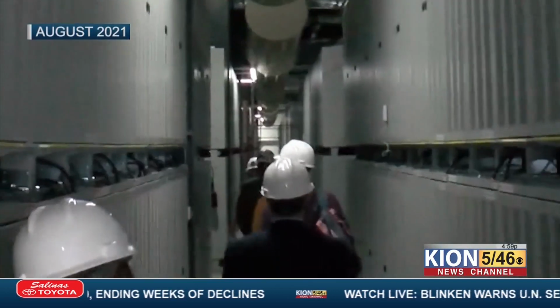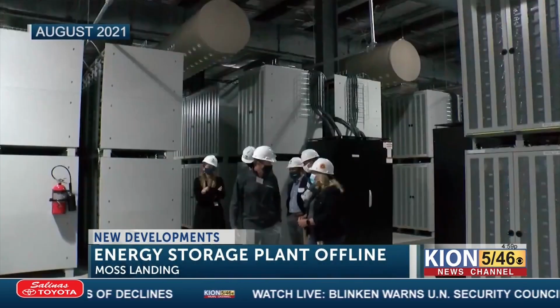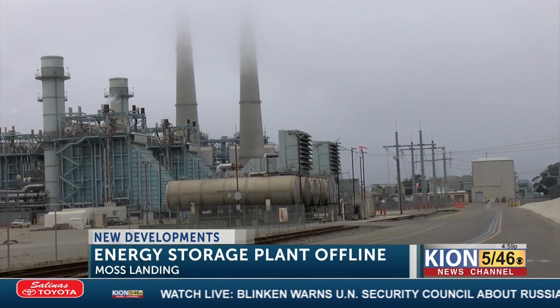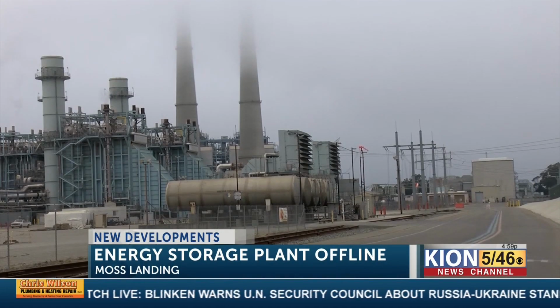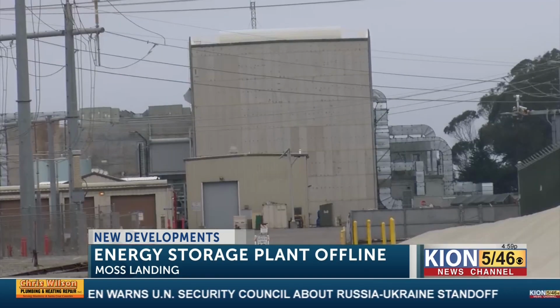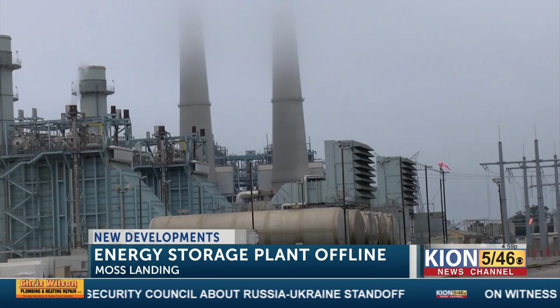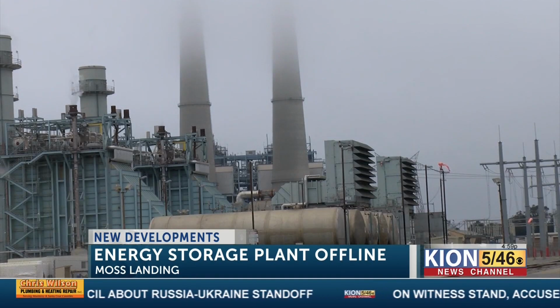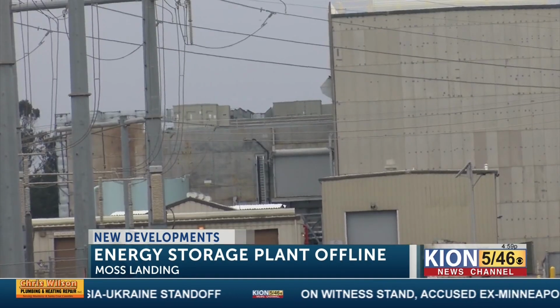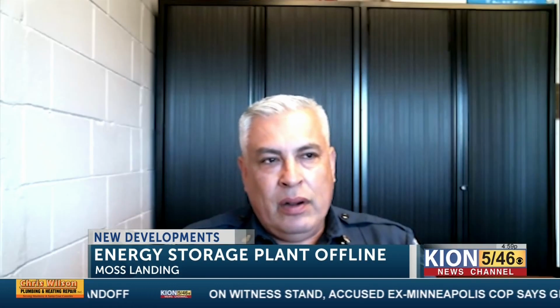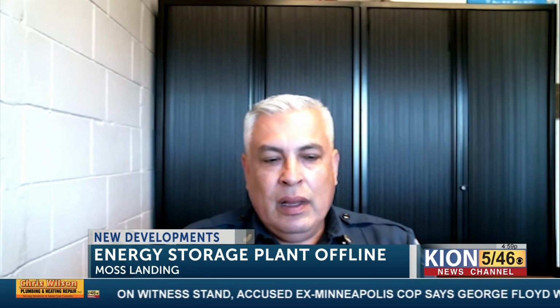The largest energy storage plant in the world is now offline indefinitely after a second overheating incident in the past 5 months. Crews with North County Fire responded to the Moss Landing plant Sunday after the early detection system was activated in the 100 megawatt phase 2 building. There wasn't any fire, but they did find that the building, the battery building itself, was charged with smoke, and there was a fire alarm, or actually a suppression system, that had armed and was actually spraying water.